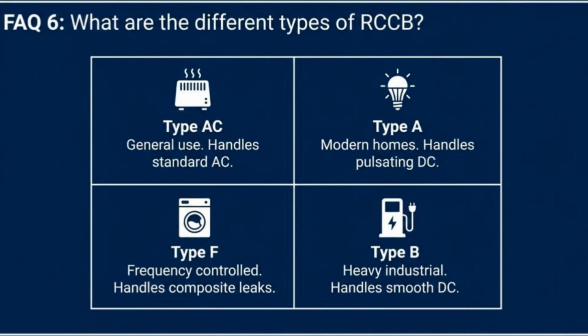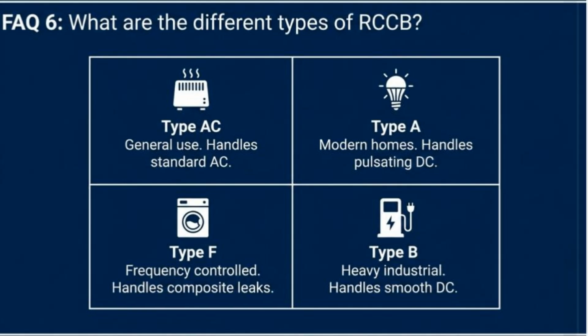FAQ 6. What are the different types of RCCB? The main types are Type AC for standard AC, Type A for pulsating DC in modern homes, Type F for frequency-controlled loads, and Type B for heavy industrial smooth DC applications.